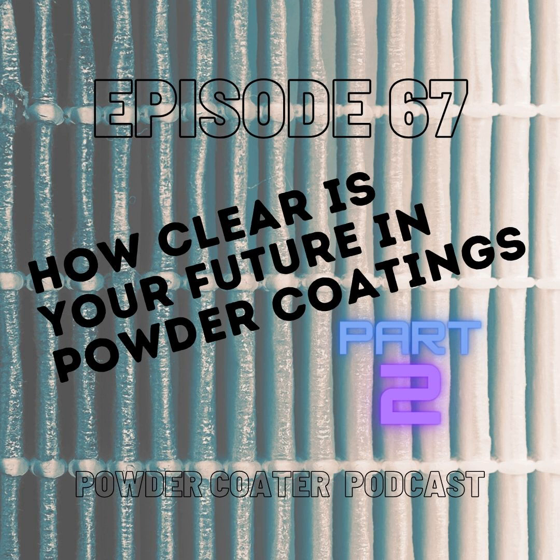The question is how. If you have an oven that you don't plan on replacing anytime soon, the first thing you want to look at is, can I turn it down? So it was designed for 450, now you're operating 350 powder. Well, you're going to turn that oven down, or you're going to run your line faster. One of the two. You're not going to leave it in there the same amount of time. So that's a very easy way to look at how you can do that. So I just looked at and just did the math.